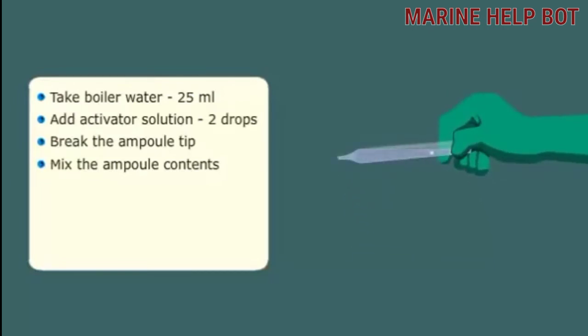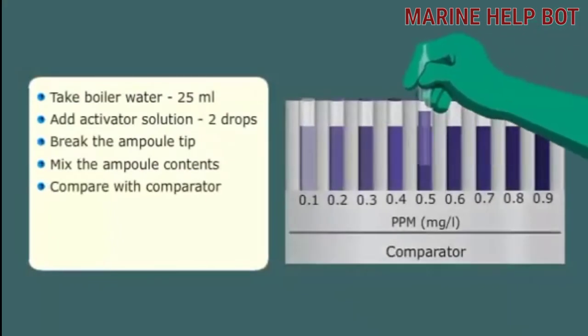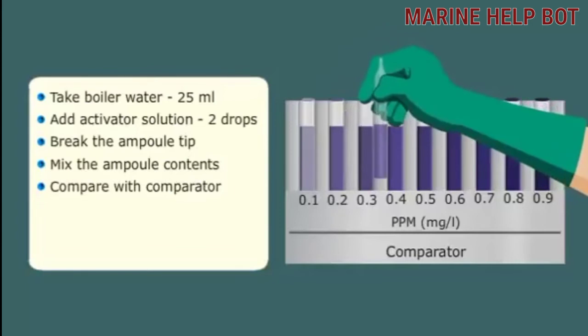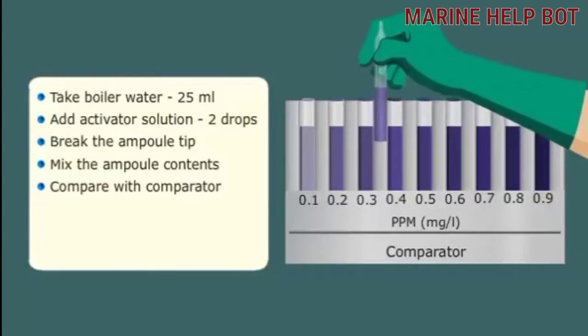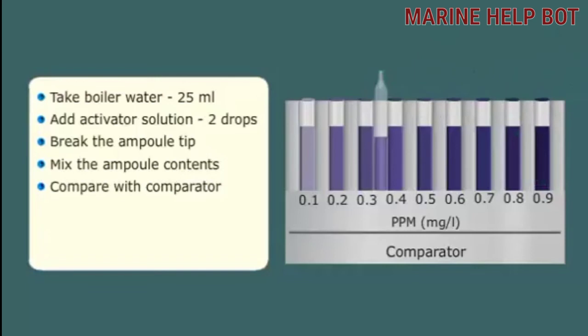Wait 10 minutes for full color development. Compare the color of the ampoule contents with the comparator's indicator color tubes. Place the filled ampoule inside the comparator. The dissolved oxygen content is given by the marking on the matching tube.